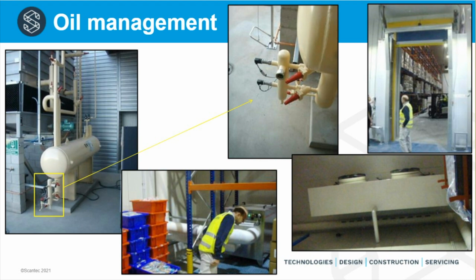What you see in the middle of the picture, this little control column, or what looks like a control column, is actually measuring the oil reservoir in the bottom of what looks like a receiver, the oil separation vessel. And when the oil reaches a certain level in the bottom of the receiver, it is automatically fed back to the compressor sump. So this is also an automatic oil return system, which eliminates oil drainage from the ammonia system as such.